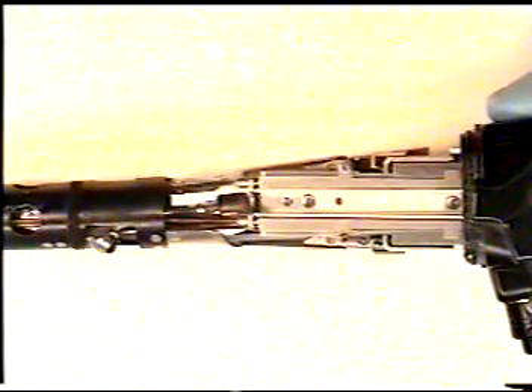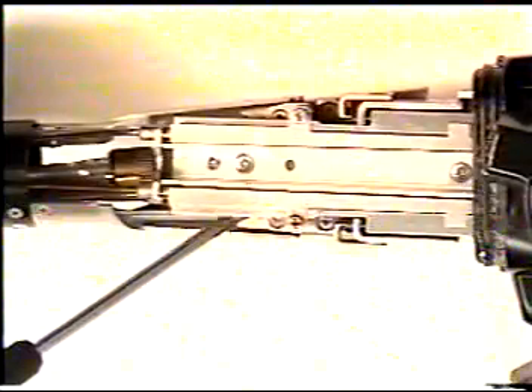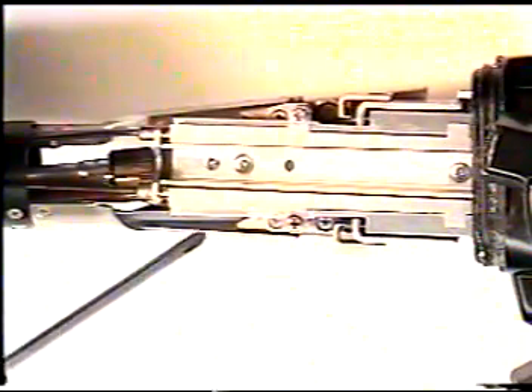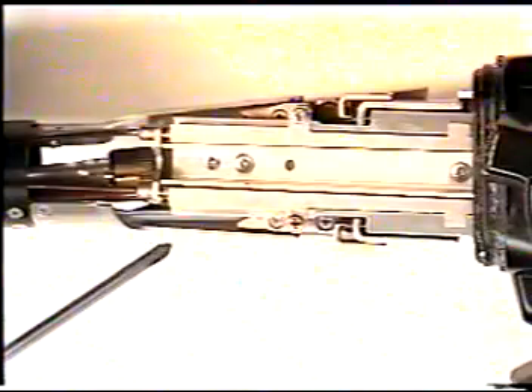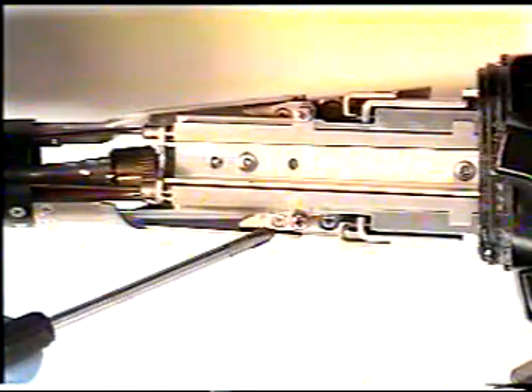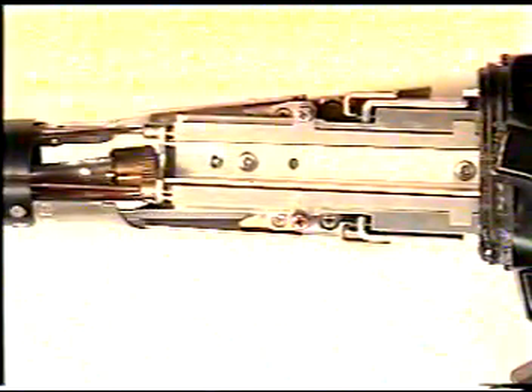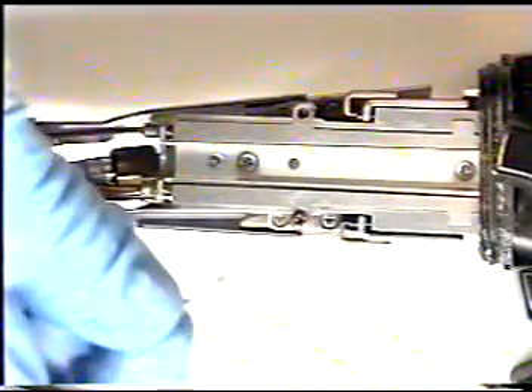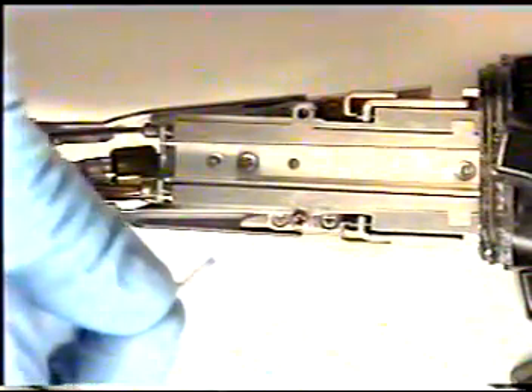We have now exposed the angulation control assembly for adjustment. Now that we have exposed the angulation control assembly, we can dismantle it to adjust the play in the cables and the angles to manufacturer's angle specifications. First, remove 2 Phillips screws from the rail assemblies. These are usually the 2 Phillips screws which have red Loctite on top of each screw head. Be sure to retain all parts removed from the body section for reassembly.